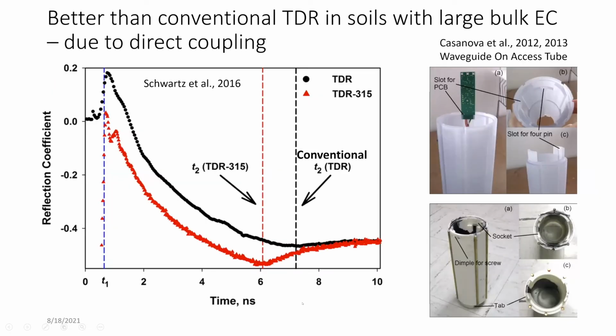And the improvement of this direct coupling of the TDR circuit itself to the waveguides is illustrated in this figure from Robert Schwartz. Conventional TDR in a very wet clay soil produces a reflection like this, where time 2 is determined to be here by waveform analysis, and there's a lot of scatter or imprecision in knowing that. Whereas the TDR-315, because it's directly coupled and there's no signal lost on a long coaxial cable, produced a very discernible reflection in a much smaller travel time. And this has turned out to be a much more accurate way to assess soil water content.